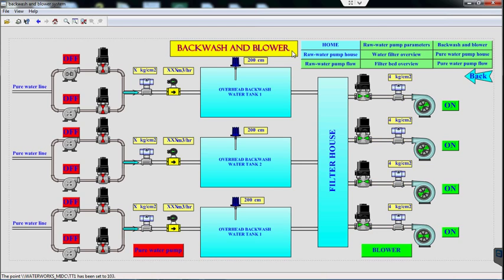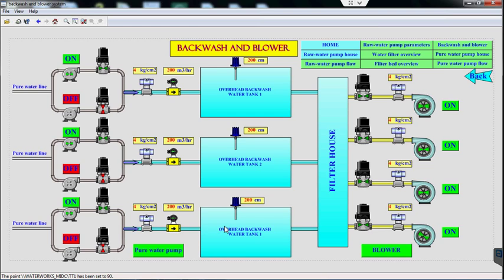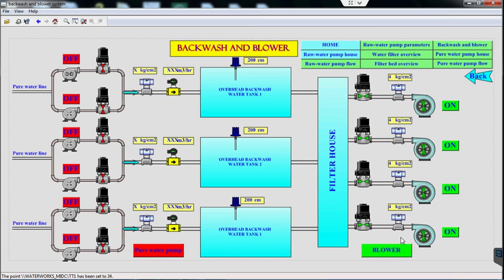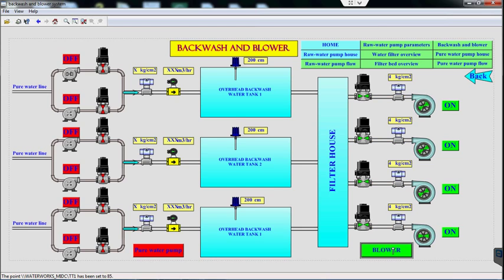Backwash and blower system. There are three sets of backwash water pumps; each set is provided with two pumps — one running and one standby. When a pump is started, pure water from the backwash water tank is delivered to the backwash water header, which is connected to each filter bed. A pressure transmitter and magnetic flow transmitter are provided at the discharge of each pump set. The amount of pure water utilized for backwash is recorded in SCADA. Four air blowers are provided and can be started and stopped from the central control room. When a blower is started, air is delivered to the air header connected to each filter bed; a pressure transmitter is provided at the discharge of each blower. A micro PLC and HMI is provided for the backwash water pump system and blowers, wirelessly interfaced with Stage 2 and Stage 3 master PLCs.